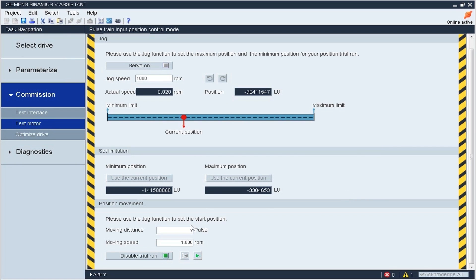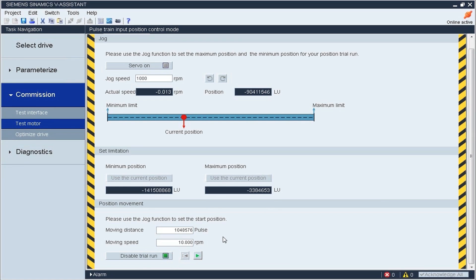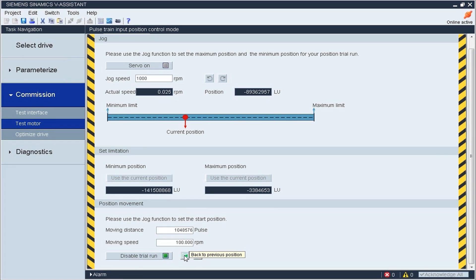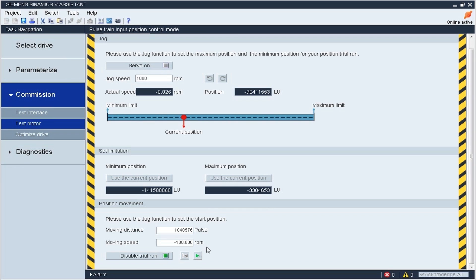After that, enable the trial operation and set the distance to be traveled and the speed. In the demonstration, the motor is with 20-bit absolute encoder, so we set the pulse number as 1048576 so that motor will rotate one circle. Please note that the distance moved must stay within the previous minimum and maximum positions that were set.